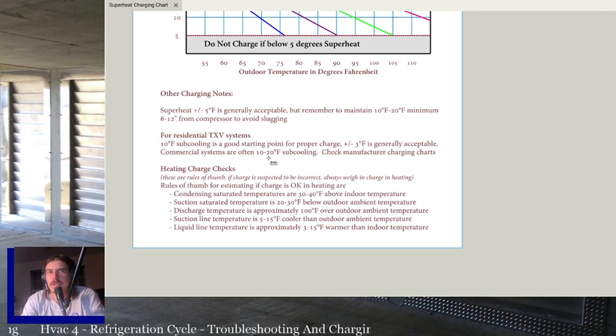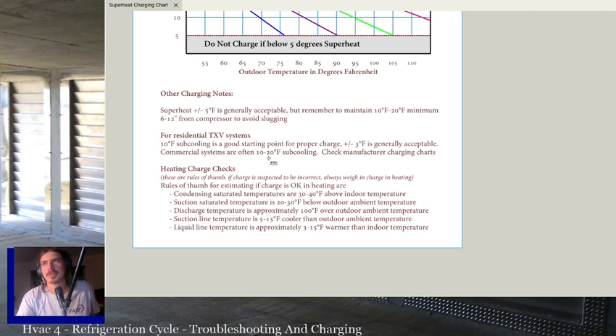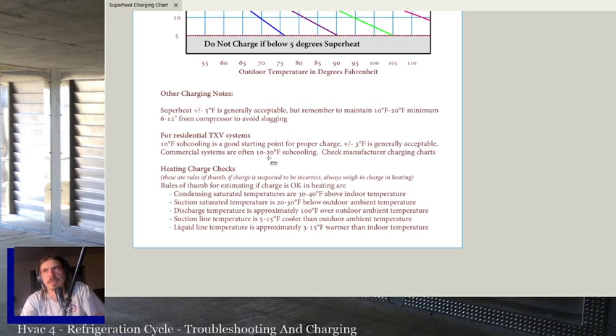Just make sure everything else is in good shape before you add that charge. If you can hit it dead perfect, hit it dead perfect. But if you've got other things you need to work out, if your superheat is plus or minus 5, just deal with other issues before you start messing with the charge, because that's going to skew everything. But remember, you always have to maintain 10 to 20 degrees absolute minimum, and usually it's going to be 20 to 30. But you need to have superheat 6 to 12 inches from the compressor to avoid slugging.